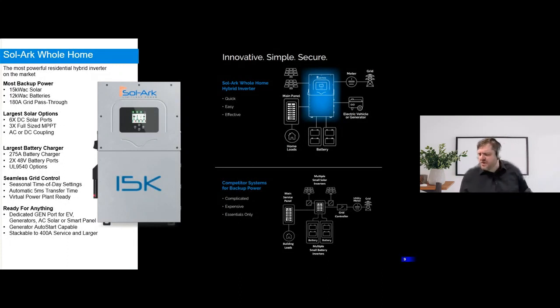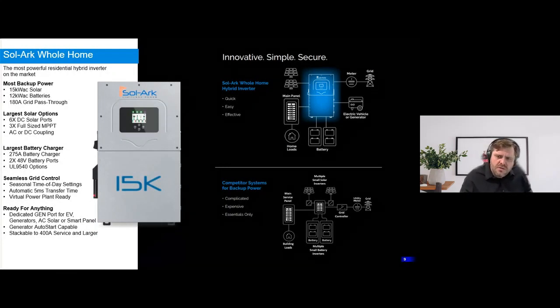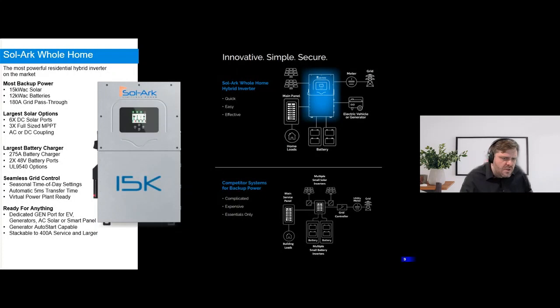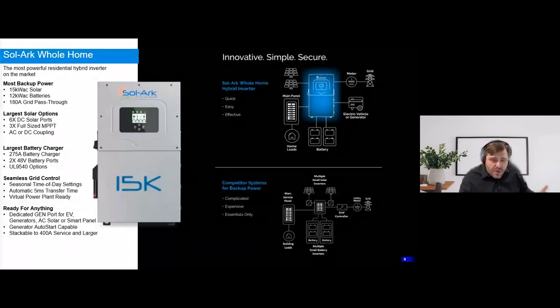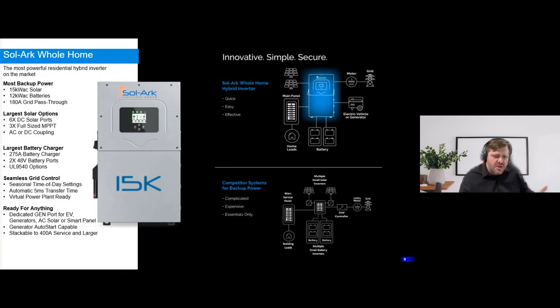For 400 amp service, what I would strongly look into is a 400 amp disconnect going to two Sol-Arks. You may want to do a fuse combiner block before then. You could also do two 200 amp disconnects and then combine those disconnects at the meter. So a little bit of design flexibility there.